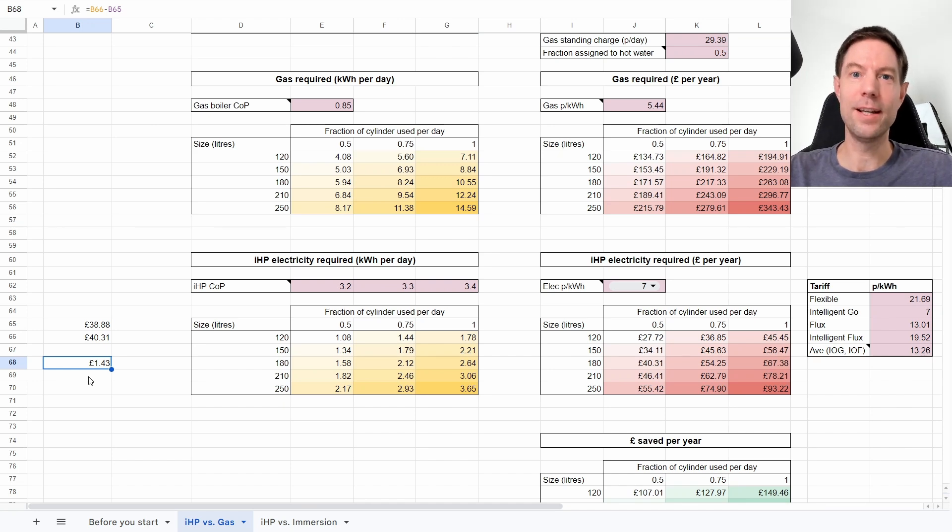So you can see why based on this calculation I'm pretty happy to accept the fact that our cylinder is installed in the garage and it really won't make very much difference at all to the amount of energy we require and the amount of cost it takes to heat that cylinder up, in addition to what it would have been if it had been installed in the airing cupboard.